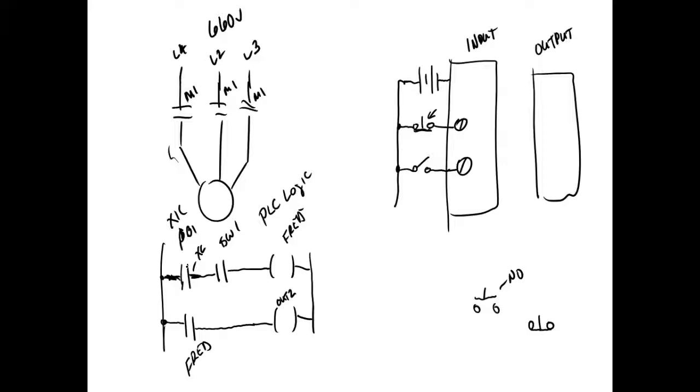That's not exactly true. A lot of times for an e-stop button, inside the PLC program, we would use one of these buttons. Because when you hit that button, it opens and you want it to close the circuit. So I'm not going to say you're never, ever going to run into an examine if open for a normally closed switch.